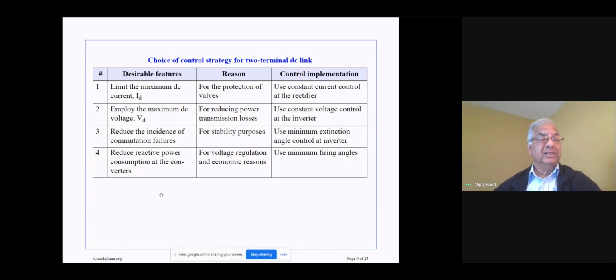The fourth requirement for the system is to reduce the reactive power consumption at the converters, both at the rectifier end and at the inverter end. The reason for that is economic: to make sure that the voltage regulation of the AC systems is minimized. And the control methodology that is suggested for this is to utilize minimum firing angles. So alpha and beta should be as low as possible. So these are the control implementation requirements which are suggested for these reasons. So how do we achieve this?